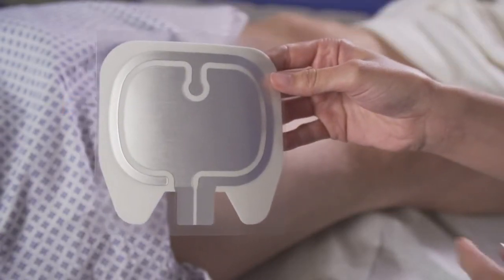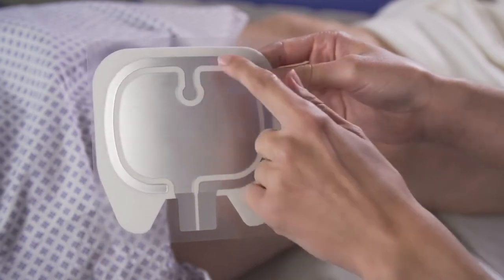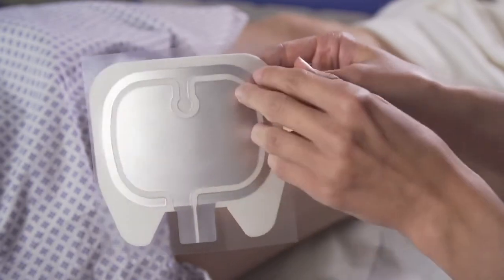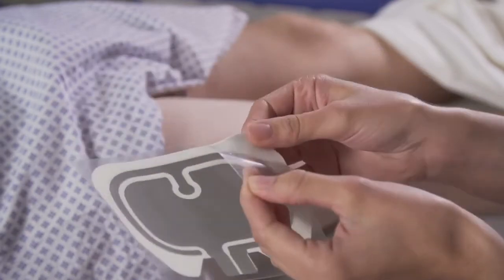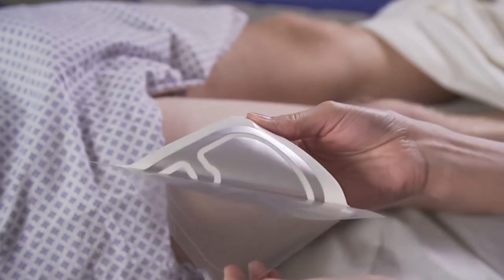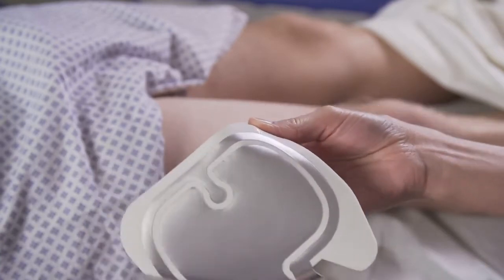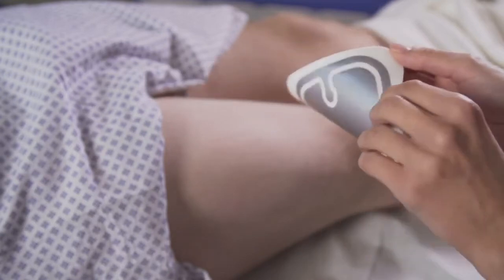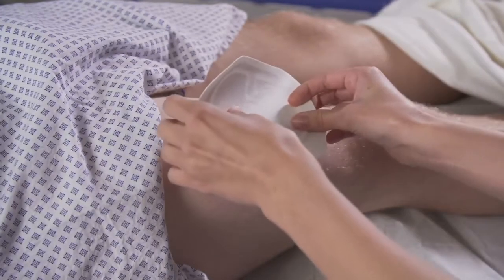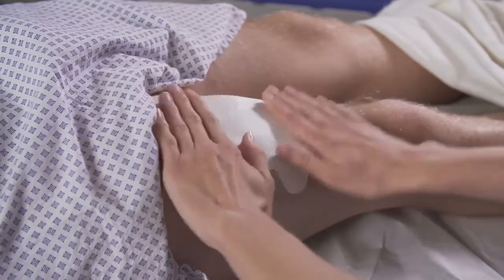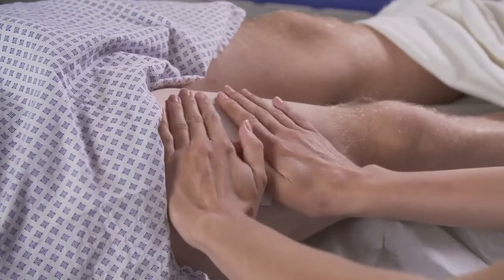When attaching the neutral electrode to the patient, important basic rules must be followed. Place it over areas of muscle with a good blood flow. Never place over implants. Remove metal jewelry and piercings. Remove thick hair for good skin contact. Ensure contact is complete over full area and press down firmly.